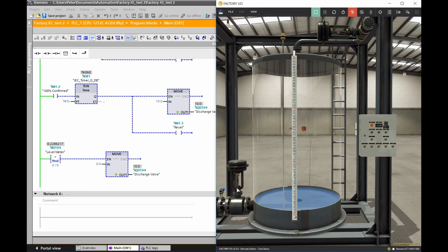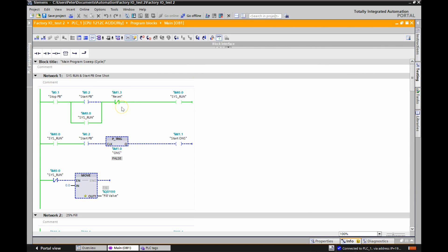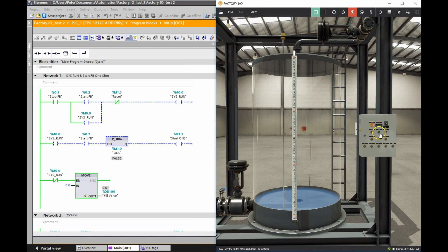The value reads 0.2624 - she's close. I had to put a threshold of 0.15 because once it gets to that water level it just takes forever to drain out. Now the value of zero is sent to the discharge valve and it closes. Scrolling up to the top of the program: the reset ran when %M1.3 was true, which kicked out my system run. So hitting this push button one more time should allow going up to 25, then 50, then 75 - the program should recycle all the way through.